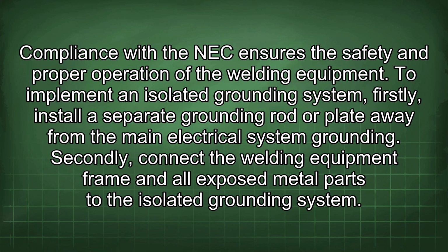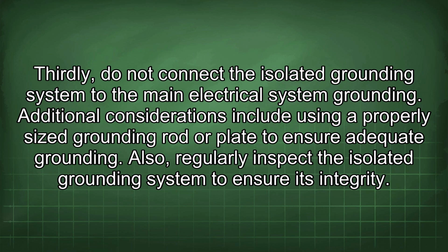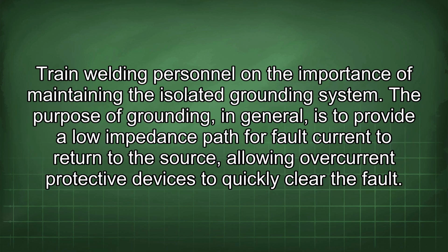To implement an isolated grounding system, firstly, install a separate grounding rod or plate away from the main electrical system grounding. Secondly, connect the welding equipment frame and all exposed metal parts to the isolated grounding system. Thirdly, do not connect the isolated grounding system to the main electrical system grounding. Additional considerations include using a properly sized grounding rod or plate to ensure adequate grounding. Also, regularly inspect the isolated grounding system to ensure its integrity. Train welding personnel on the importance of maintaining the isolated grounding system.